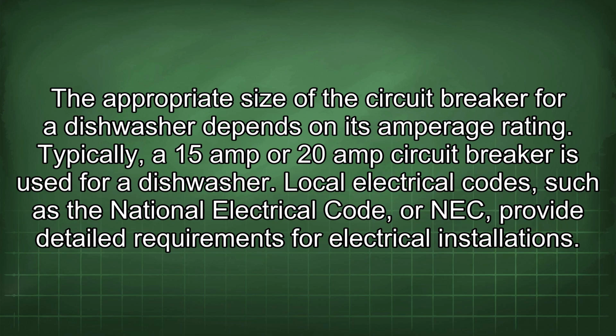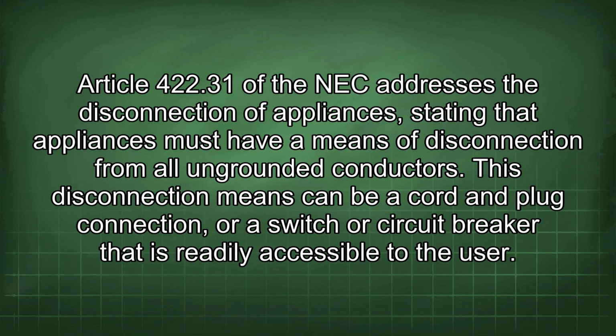Local electrical codes, such as the National Electrical Code, or NEC, provide detailed requirements for electrical installations. Article 422.31 of the NEC addresses the disconnection of appliances, stating that appliances must have a means of disconnection from all ungrounded conductors. This disconnection means can be a cord and plug connection, or a switch or circuit breaker that is readily accessible to the user.